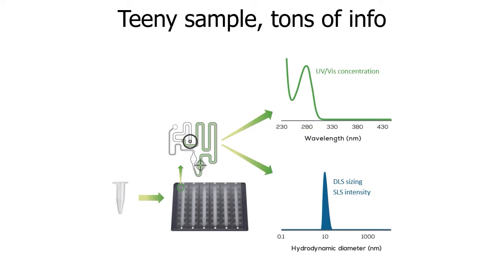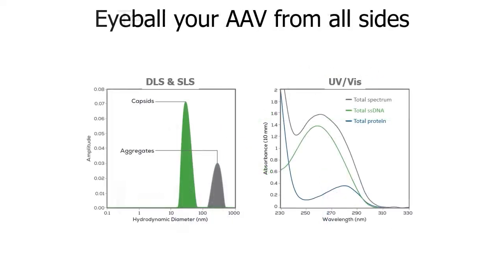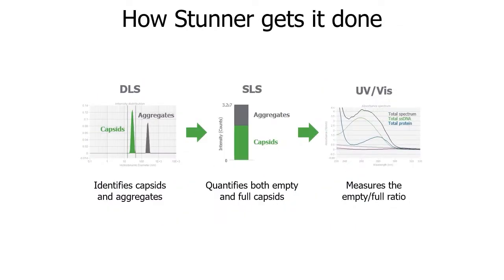With two microliters, UV-Vis is used for concentration, while DLS provides sizing and aggregation detection, and SLS — static light scattering — quantifies the amount of light coming from your sample. DLS identifies which peak is your capsid (typically around 25 nanometers) versus aggregates. SLS distinguishes how much of the signal comes from true capsids versus aggregate components, giving you more reliable measurements. UV-Vis then determines the nucleic acid component and total protein, from which you derive the empty-to-full ratio.